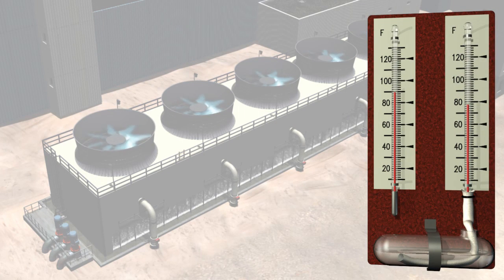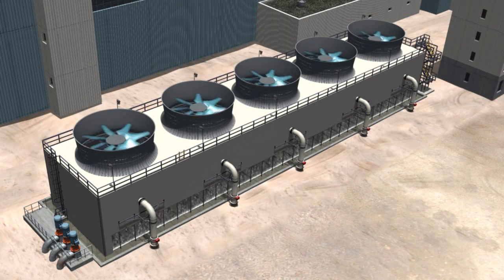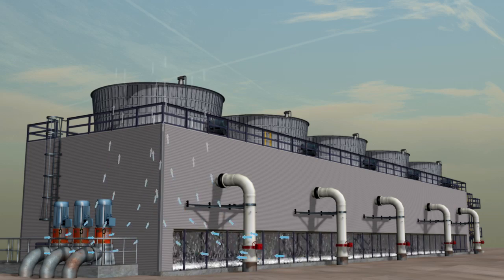As the wet bulb drops, the tower performance will increase and fans and pumps can be cycled to the off mode, leaving only one pump operating. This will result in very low water loading across the entire fill media. This, coupled with the warm water, will create a natural flow of air. The tower operating in this mode essentially becomes an efficient natural draft cooling tower.